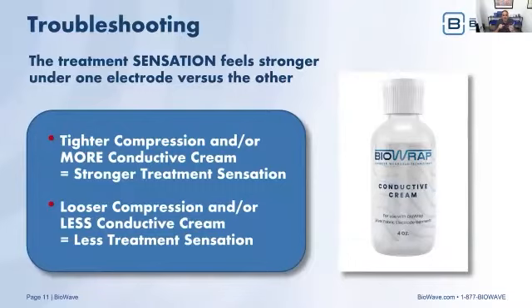So let's say it feels much stronger just proximal to the ankle versus how it feels around the foot. In that case, you could loosen the compression on the ankle to make it feel less strong. This is if you want it to feel stronger on the foot relative to the ankle. You could also remove the BioWrap, add more cream around the foot, then put the BioWrap back on, see how it feels. If the ankle still feels stronger, just make the compression tighter on the foot and less tight on the ankle. So those are the two variables you have to adjust the sensation in both those locations to either make one stronger versus the other, or to make them feel the same, depending upon whether you're trying to treat the entire foot and ankle, or you want to be more focused on the foot, or more focused on the ankle. And this is the conductive cream, this image here that comes with your BioWrap.